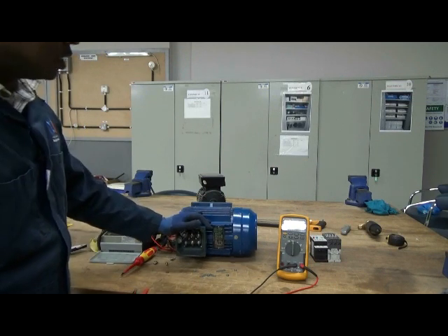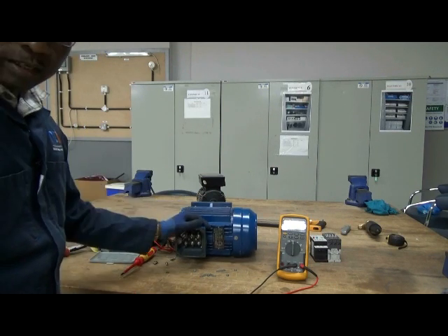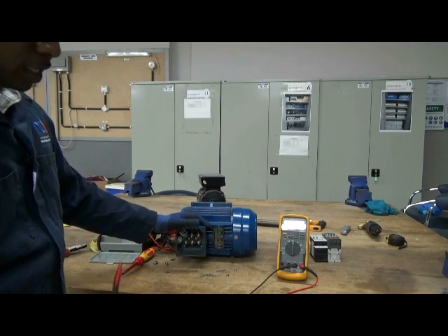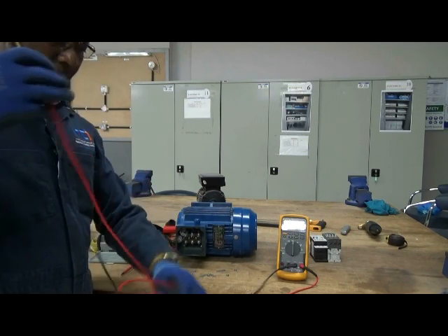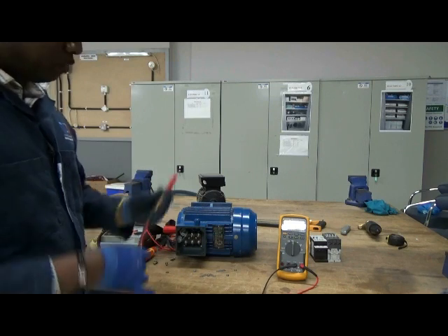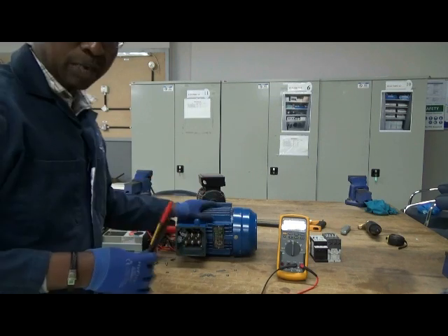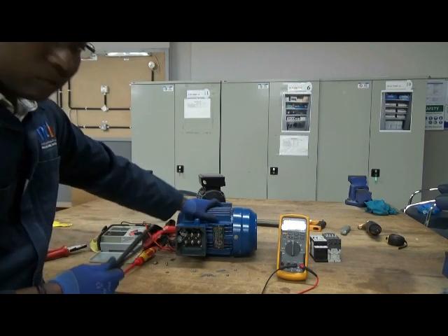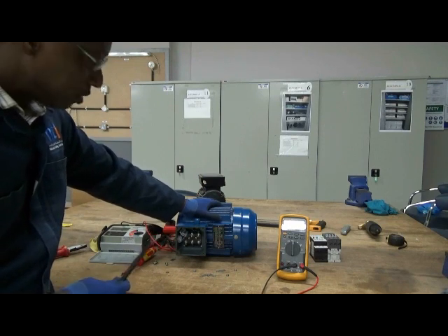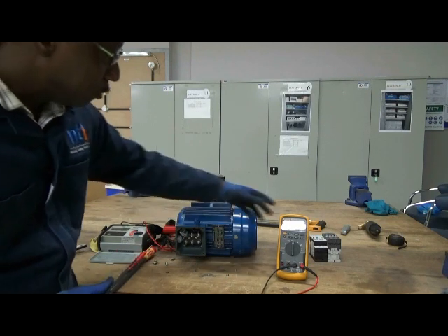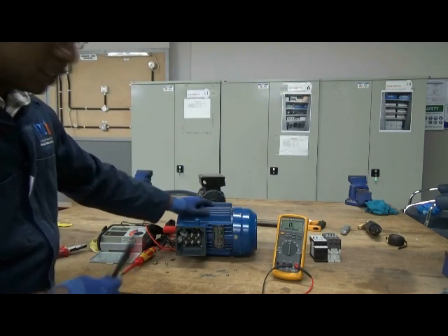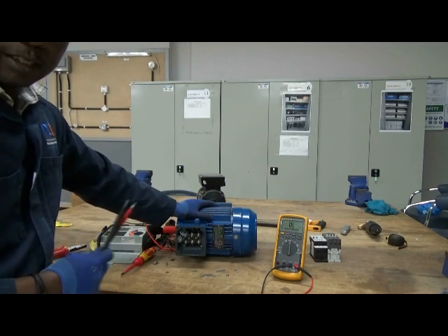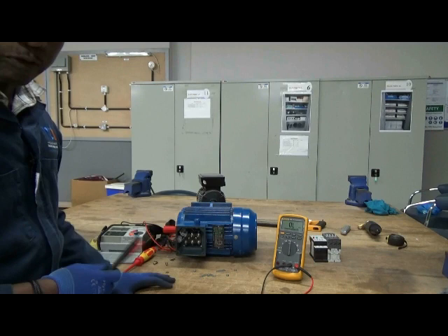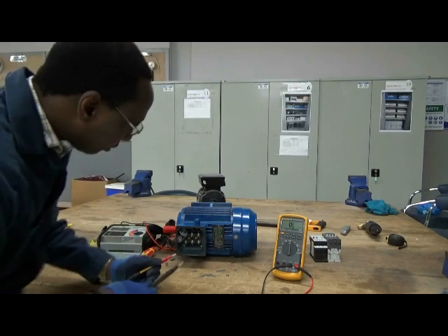Now I'm going to carry out the measurement of the winding resistance using a multimeter. The Fluke type is the best type you can get almost all over the world. So we have here a Fluke 87, and this instrument can assist us in determining the resistance of each winding. So I'll start off with the first winding.